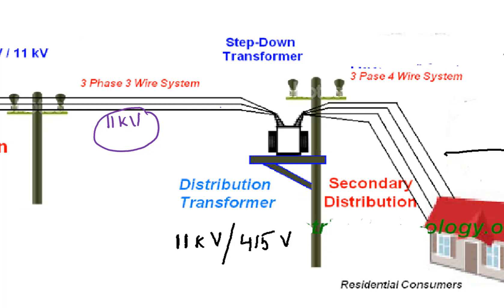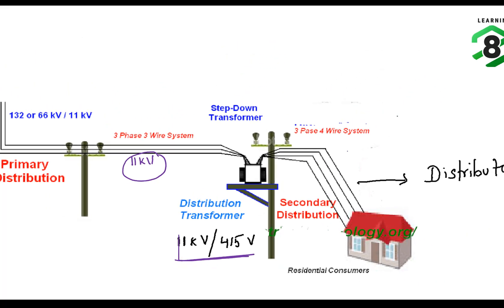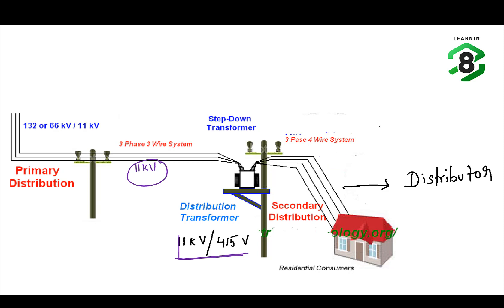There is then a step-down transformer that steps down the voltage from 11 kV to 415 volts. The nominal voltage of that three-phase, four-wire distributor is 415 volts. At every point in the network, there is a specific voltage which the system has to maintain — that voltage is called the nominal voltage. It is always expressed as a line-to-line RMS value, though the actual voltage may vary slightly from it.